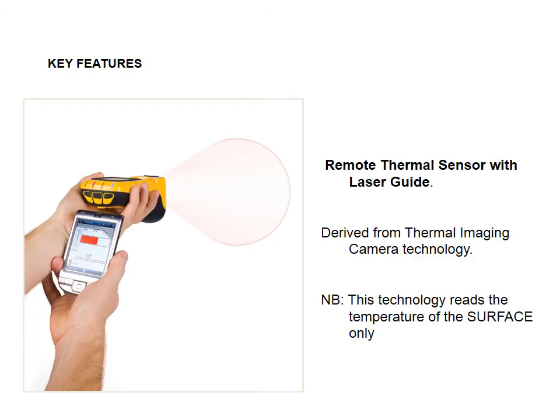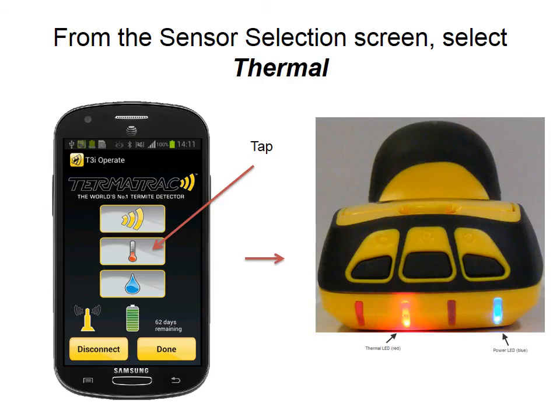We'll now talk about the thermal sensor on the T3i device. It is the same technology used in thermal imaging camera technology. This technology on the T3i, as with thermal image cameras, only reads and measures surface temperature, and does not penetrate beneath the surface. When you tap on the thermometer icon for the thermal sensor, a red LED will appear on the unit as well.